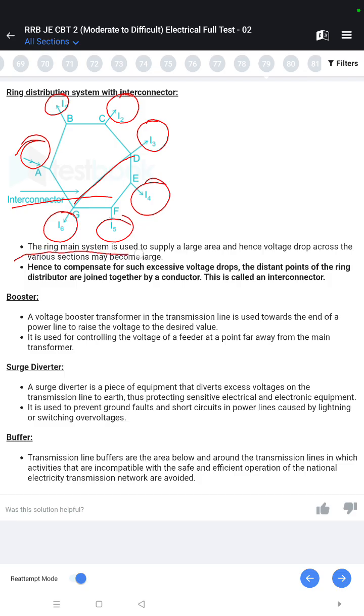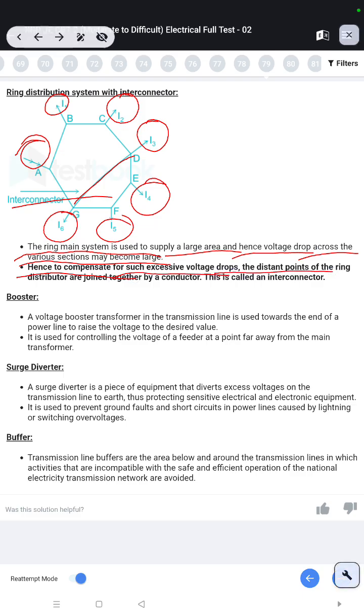The ring main system is used to supply a large area and hence voltage drop across the various sections may become large. Hence, to compensate for such excessive voltage drop, the distant points of the ring distributor are joined together by a conductor. This is called an interconnector. Booster.